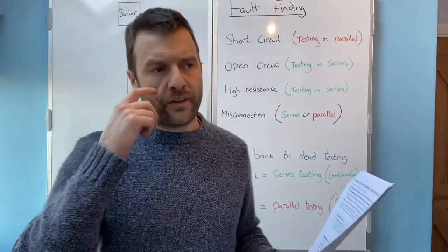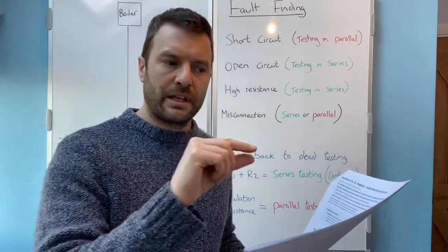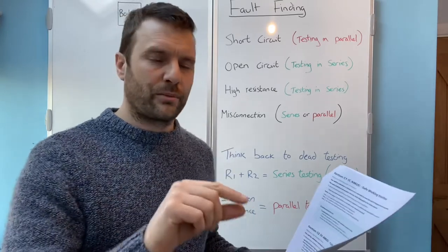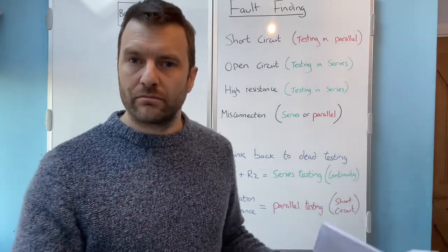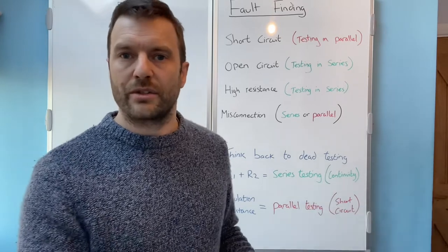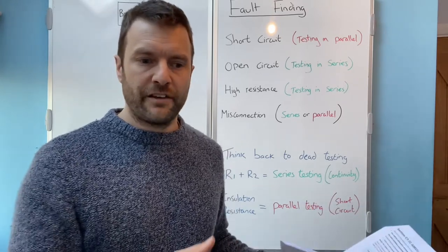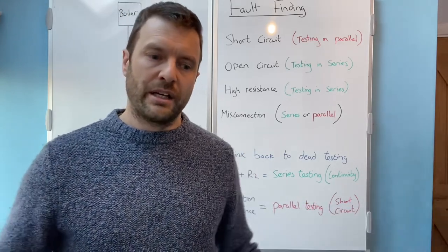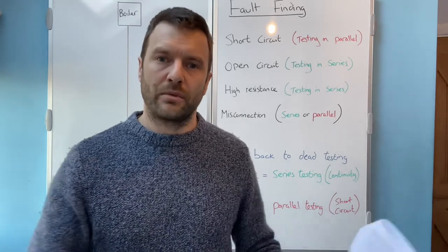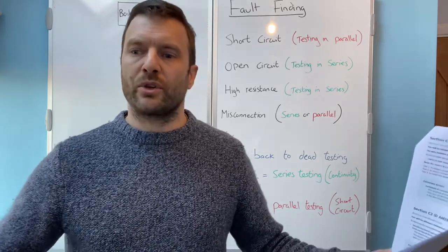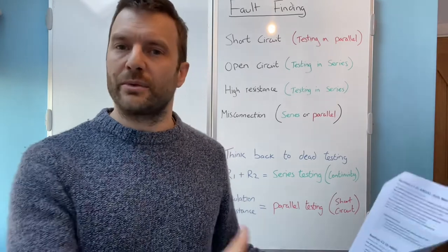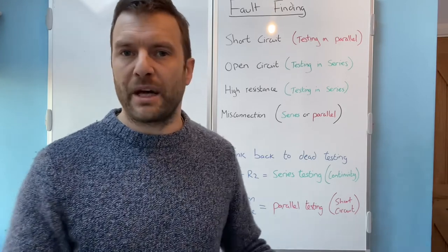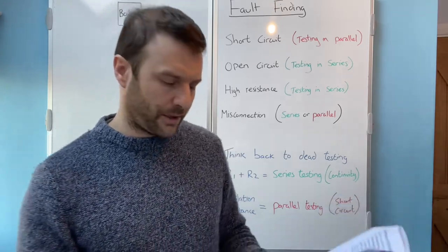And again, in a real life situation, we always start off with the easy fix, okay? So obviously safe, easy fix, not bodging it. But if it's a loose connection, then we literally just want to tighten up the loose connections, retest, off we go. If it then requires testing of the cable, when you find out the cable's destroyed, that is then replacing a piece of cable between two points. What you don't want to do is quote for a rewire when all you needed to do was check some connections, costing the customer thousands of pounds for £10 worth of work. That's the level that you need to think about.